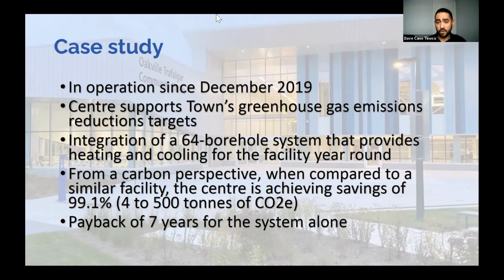Total capital costs of the project were a bit over $1 million, plus additional funding required to integrate the geo-exchange system into the facility. Based on the numbers I provided, and including the cost of the carbon tax, which will reach $170 per ton by 2030, we get an operational energy cost for OTCC of $240,000 annually. Community Center 2 has an operational energy cost of $397,000 annually, a difference of $157,000 per year. Using these numbers, we get a simple payback of 7 years for the system alone.